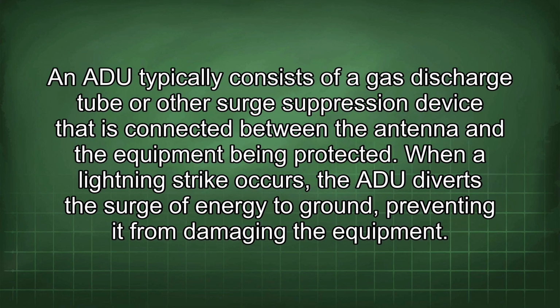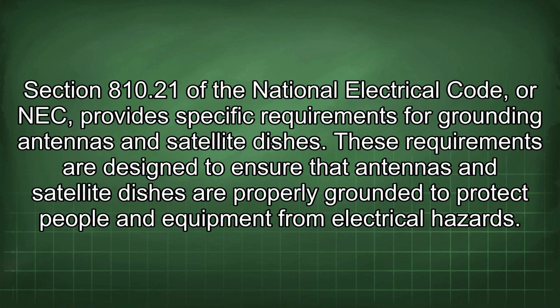An ADU typically consists of a gas discharge tube or other surge suppression device that is connected between the antenna and the equipment being protected. When a lightning strike occurs, the ADU diverts the surge of energy to ground, preventing it from damaging the equipment. Section 810.21 of the National Electrical Code (NEC) provides specific requirements for grounding antennas and satellite dishes.